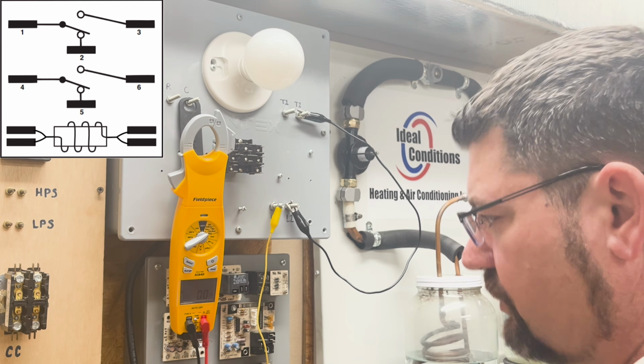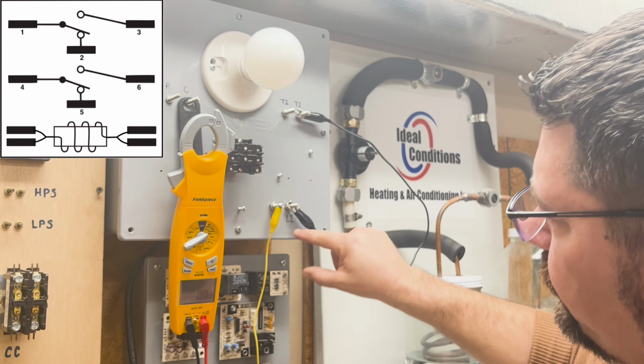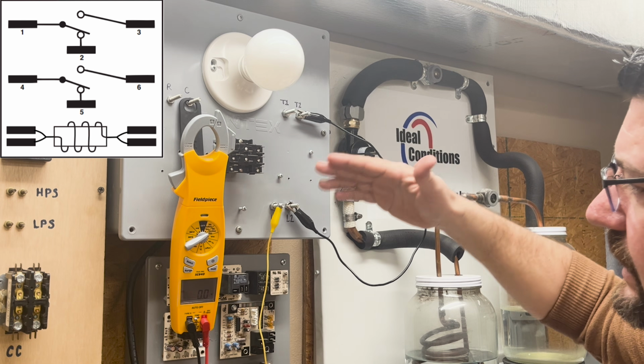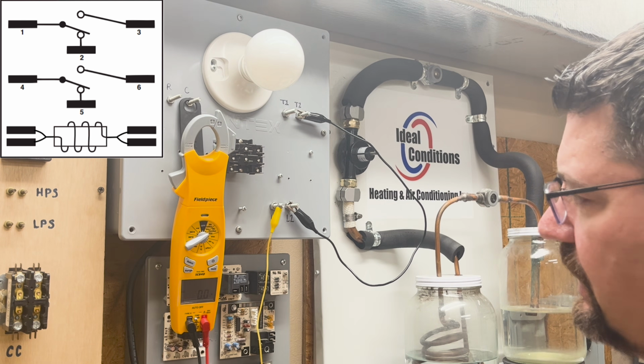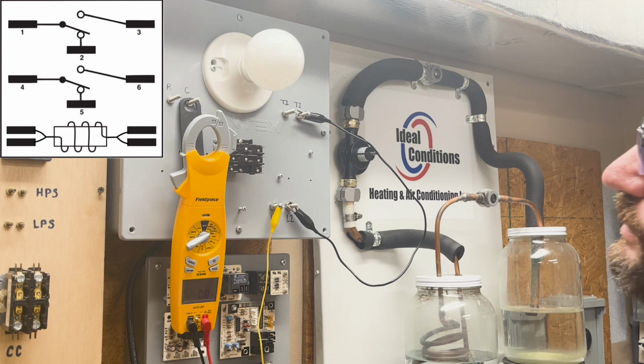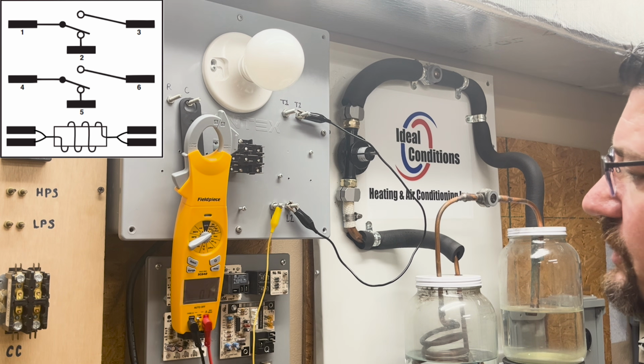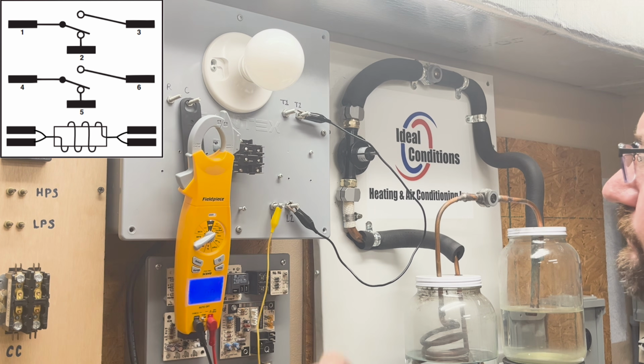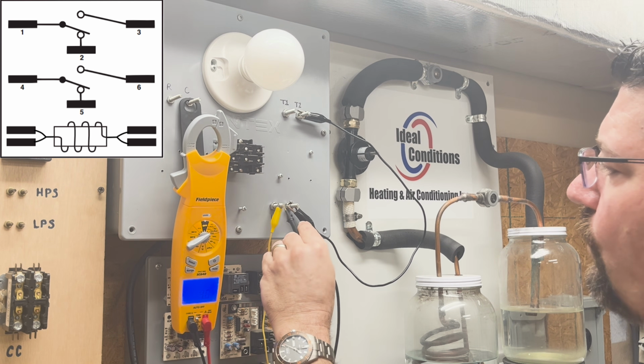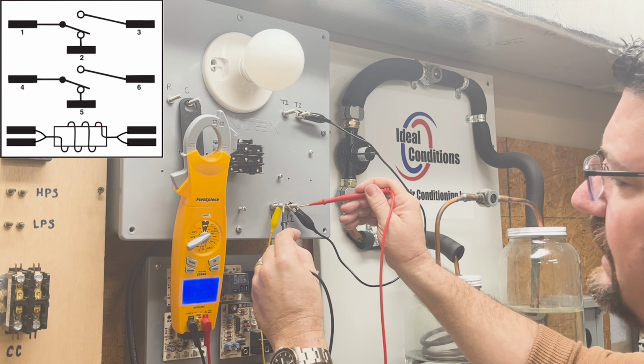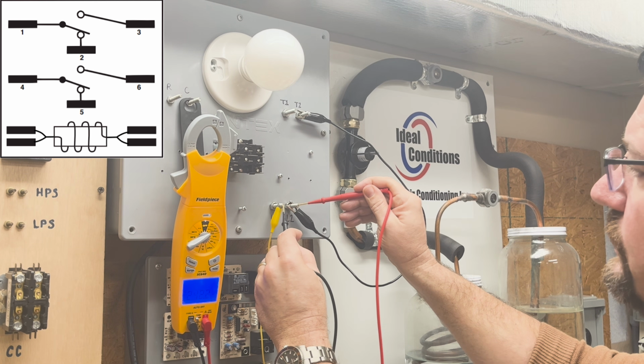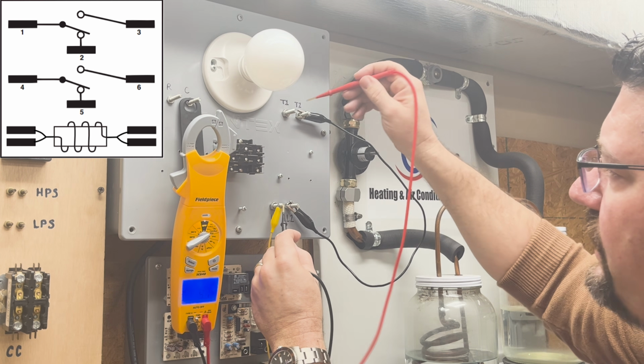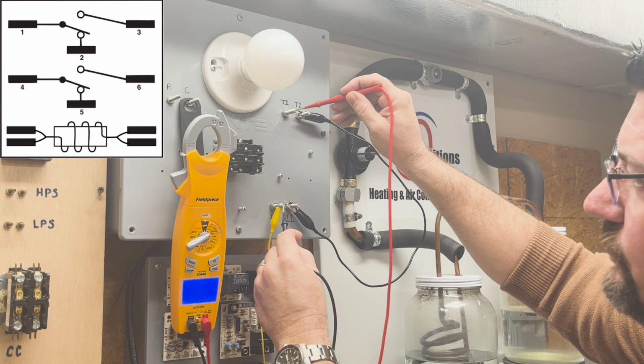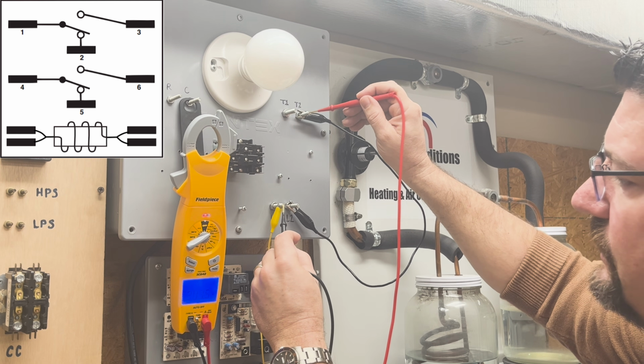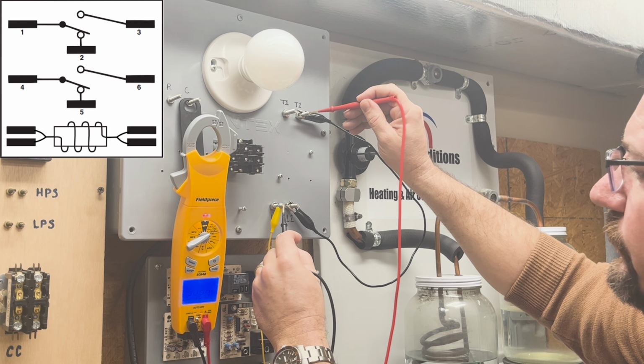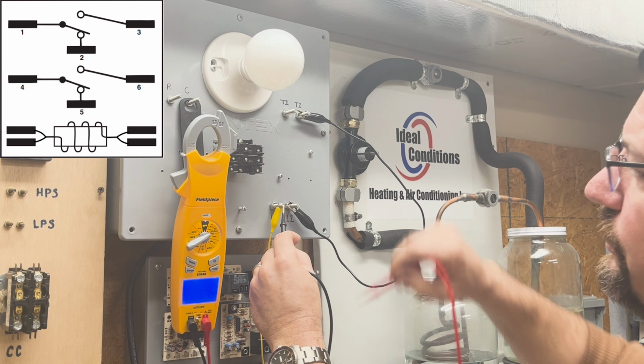I'm going to come down here to show you that because we wired L2 to T2 without the relay, and we don't have L1 to T1 up there, there's no load on. But that doesn't mean there's no power present - if I put my light back on and go between L1 to L2, you'll read a difference of power of 241 to 242 volts. If I kept one lead here and went up to T1, I still have 240 volts. And if I went over to T2, I have 243 volts. That's because L2 is present all the way through the load.